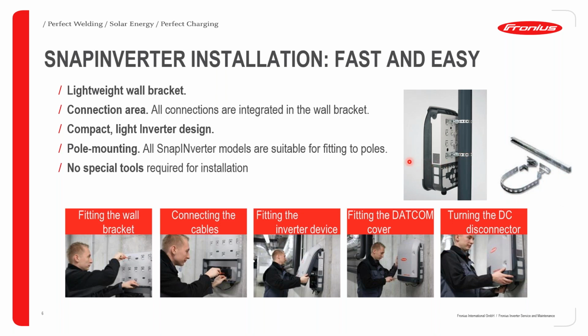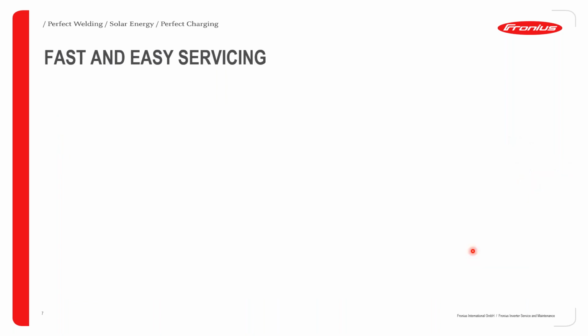No special tools are required for the installation. So long as your preparations are done, all you need is a screwdriver: screw down the wall mount bracket, connect the cables, fit in the inverter device - or as we fondly call it, snap in the inverter device onto the wall bracket - then fit in the DATCOM cover, turn on the DC disconnector, and you're done. It's that fast and that easy.